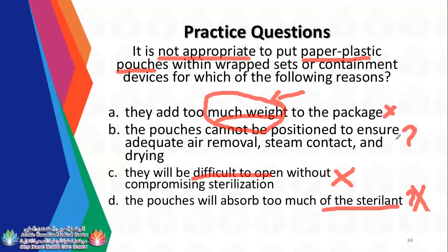Okay? And even if you will fit it in the right position, it is not appropriate to put another specific pouch inside, especially when you already have a containment or a protective container for your instruments. So if you need a specific container, for example for small items, you need to put them in a perforated tray, a small tray, which is intended for use together with the rigid container.